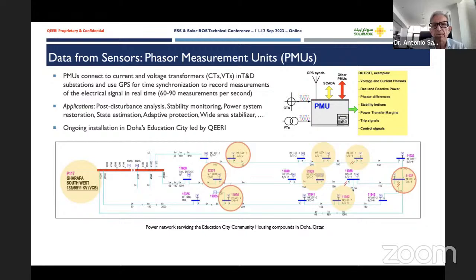These are a class of devices that are becoming more and more popular to collect data from the electrical signal data in real time. We're talking about 60 to 90 measurements per second that typically are installed in the current and voltage transformers in the substation, distribution and transmission substation, and use GPS for time synchronization. A lot of applications can be developed using this data, post-disturbance analysis, stability monitoring, and so on and so forth.